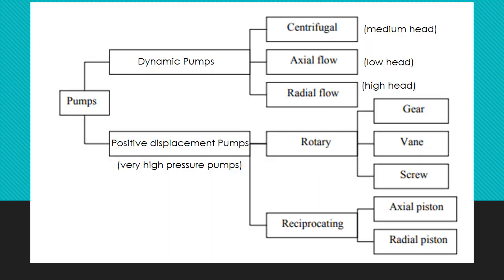Pumps can be divided into two categories: dynamic pumps and positive displacement pumps. Positive displacement pumps are generally very high pressure pumps and they can be further divided into rotary and reciprocating pumps. Reciprocating pumps are basically of three types: plunger, diaphragm, and piston pumps. Rotary pumps can be further divided into gear, vane, and screw pumps.